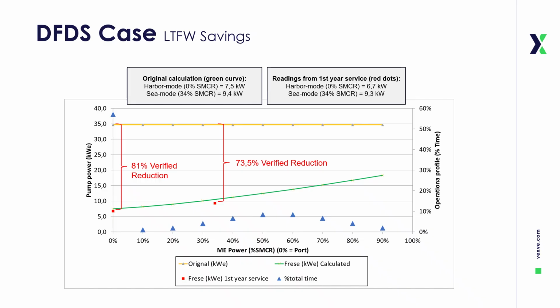Under these part load conditions, static valve control forced the pumps to continue operating at design capacity, resulting in substantial overpumping and wasted energy. With Frese FUELSAVE optimization, the pumps were allowed to follow real demand. Flow was reduced in proportion to the cooling load, cutting pump energy consumption by up to 81% in harbour mode and 73.5% in seagoing mode compared to the static baseline in yellow colour. These verified results confirm that aligning pump operation with actual SMCR-based load conditions delivers both fuel efficiency and compliance benefits, while maintaining full cooling reliability across all consumers.